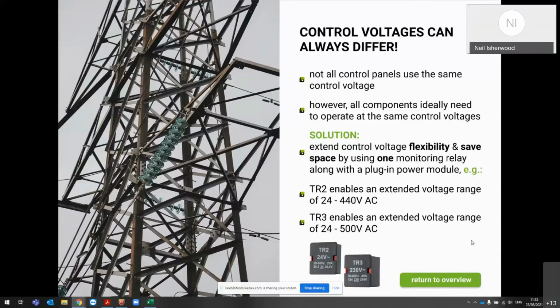Say in your cubicle you want a voltage monitor and a current monitor, but you may want a few different current monitors monitoring different things. What you can do is take the Gamma device, and these two black modules at the bottom, we call them TR2 and TR3. Depending on the width of your product, if you've got a 22.5 millimeter product, you just take a TR2, and that ranges anywhere from 24 volts all the way up to 440 volts AC.